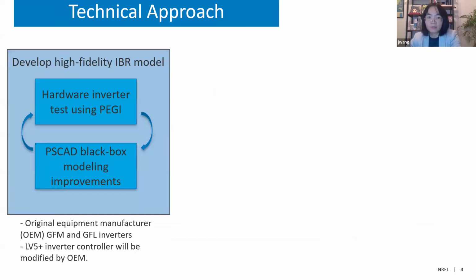The next diagram will show you the technical approach. First, we use the hardware inverter as a benchmark and test how the PSCAD black box model matches the hardware inverter. We have both grid forming and grid following inverters to validate. We run through different dynamic studies such as LVRT, HVRT, ROCOF, impedance scan, and also phase jump, those typical tests people usually do for model validation. We have multiple iterations of changing inverter settings and control parameters, and also DC modeling and the transformer. After that, we finally got a very well matched model.